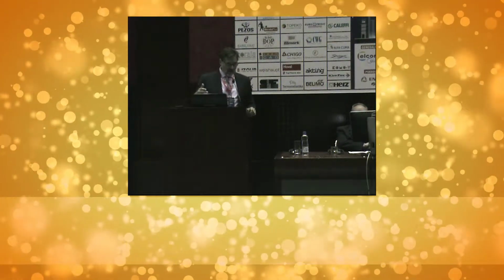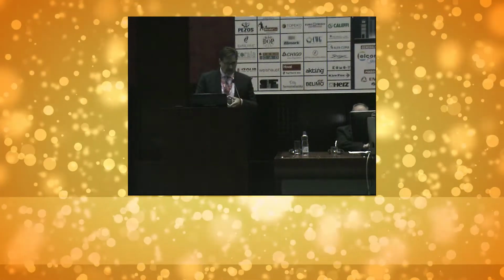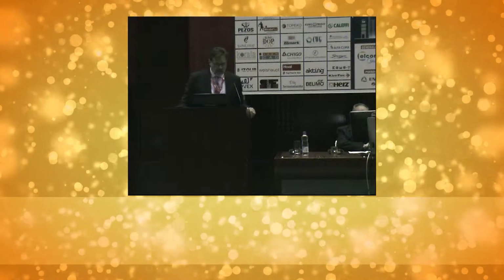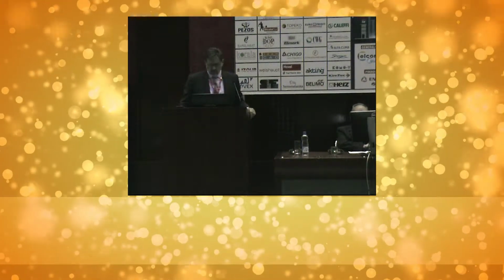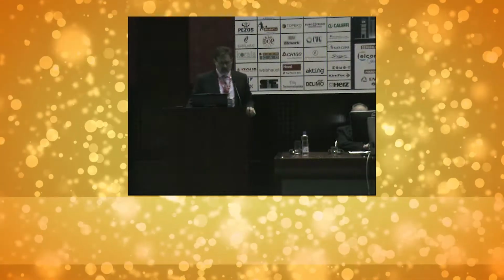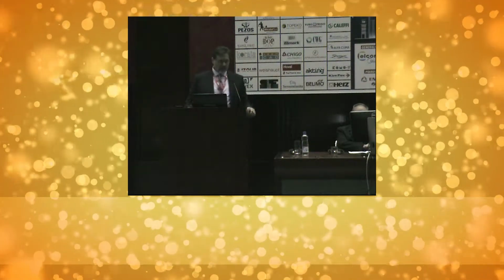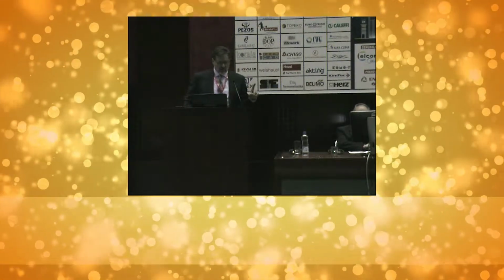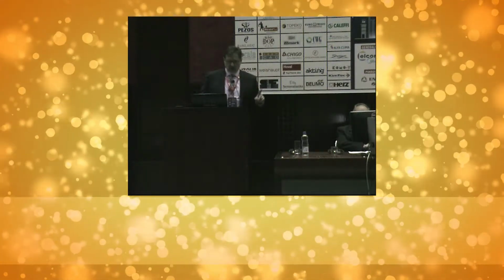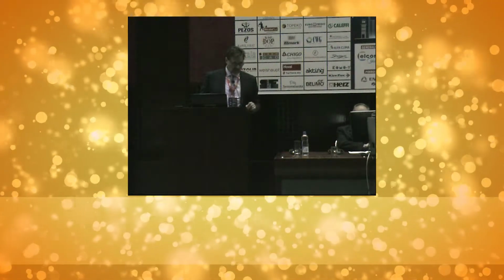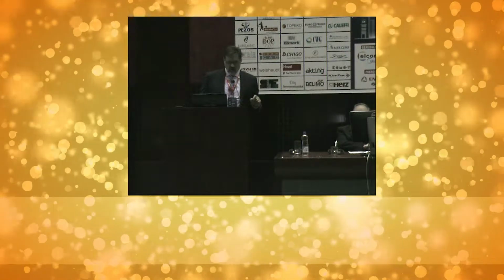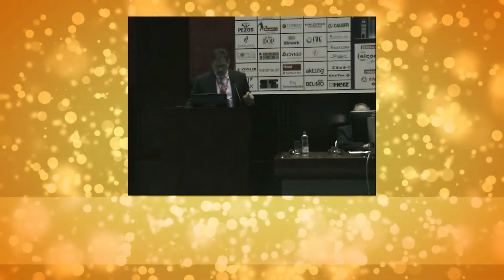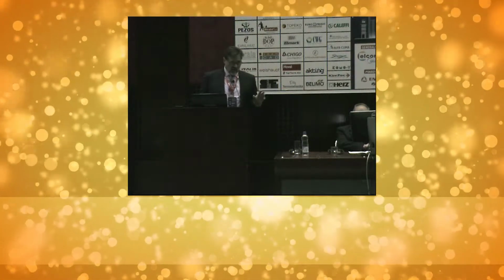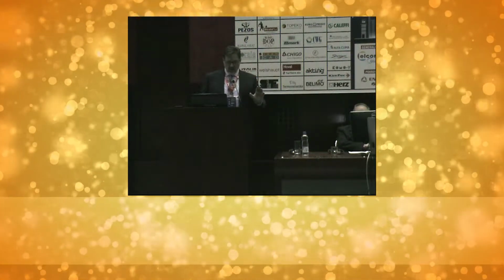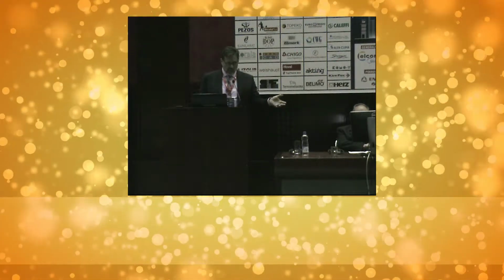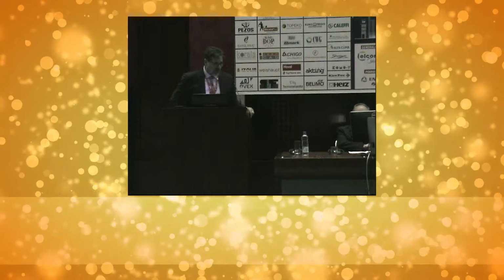So this is the couple things that I have to worry about. If I undersize, I'm gonna of course have bigger pressure drops, I'm gonna have sound losses and so on. I don't think I have time to go into all this criteria, but let's go to the selections. The first thing that I pay attention to is basically the total pressure drop on the box, not the static pressure as most of the people would mislead you with. You gotta understand only total. And when we were establishing this, we based our inlets on the 2,000 feet per minute, which is your velocity through it. And then due to the delta P, or the pressure drop, you really don't want to exceed the 0.35.